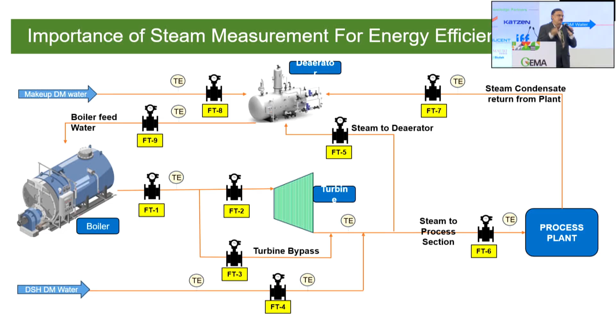So it is very important to measure consumption at each of these points, having measurement devices like flow transmitters and pressure transmitters to properly understand the consumption points in the plant. It's also important to measure how much steam is actually going into the process plant's steam header, in terms of both flow and pressure, and then beyond the steam header, how much steam is going into all the consumption points — measuring steam flow and pressure at each of them.